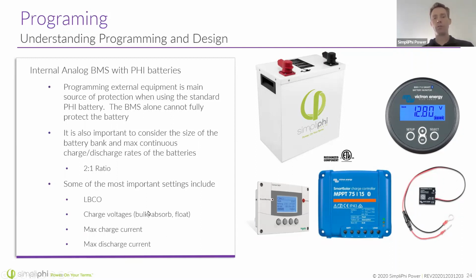charging voltages, right? So the BMS is expecting different voltages for the charging cycle, and that helps to maintain the health of the battery. Bulk charge is when you're charging at a constant current at the beginning of a charging cycle. Absorb charge is when the battery is left at that voltage for a certain amount of time. For our batteries, it's 10 minutes at 56 volts. And then float charging, you really don't need to do this for lithium batteries.